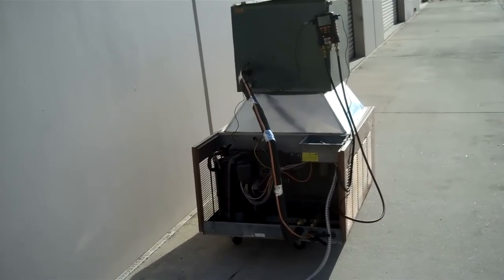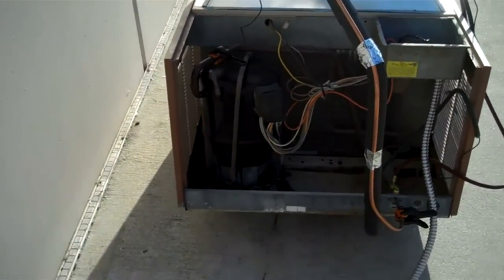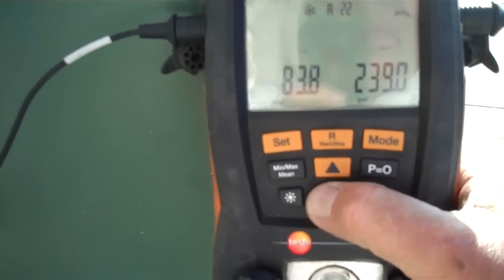I think I'm pushing 13s here with this thing. Look at the suction line temperature — 53. The compressor is loving it. This thing is fine-tuned. I actually had to clean a condenser coil because my discharge was so high — I didn't think it was going to work. I had a dirty condenser coil, so I had to take it all apart and clean it. I got my head pressure to drop, and I think I'm right on target.